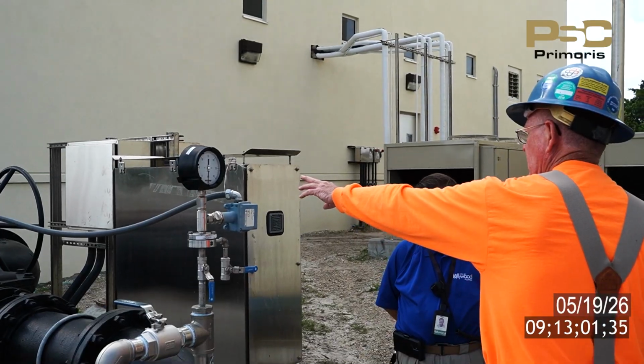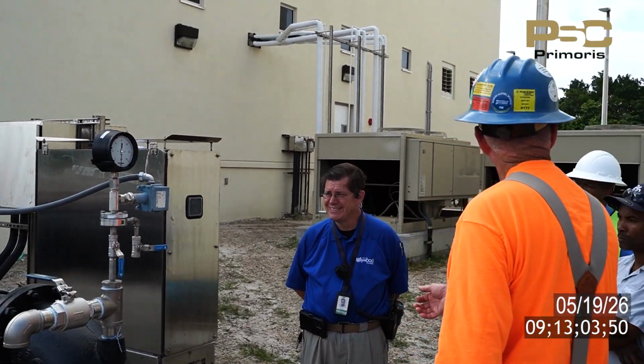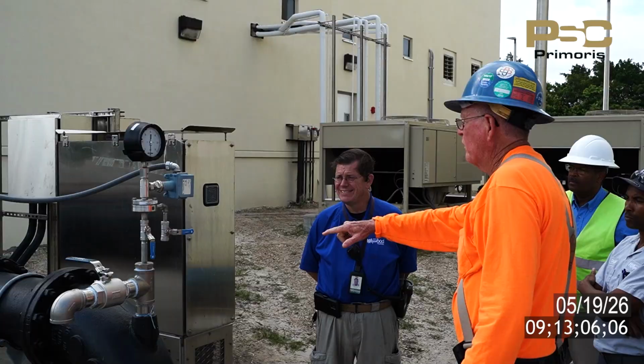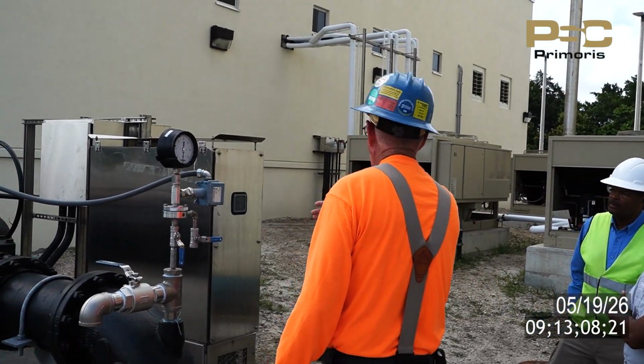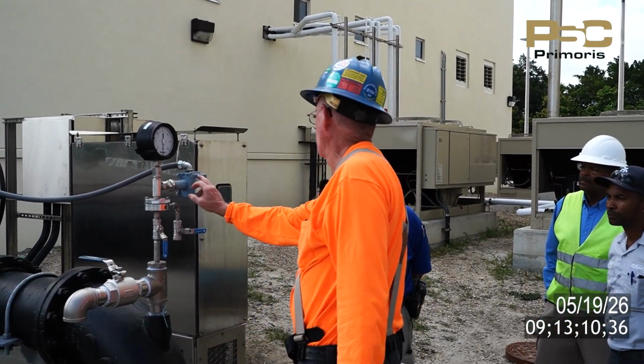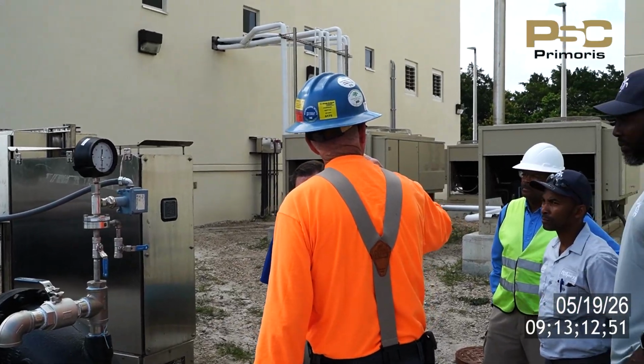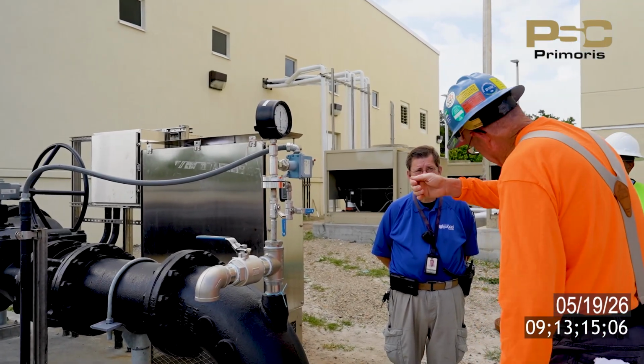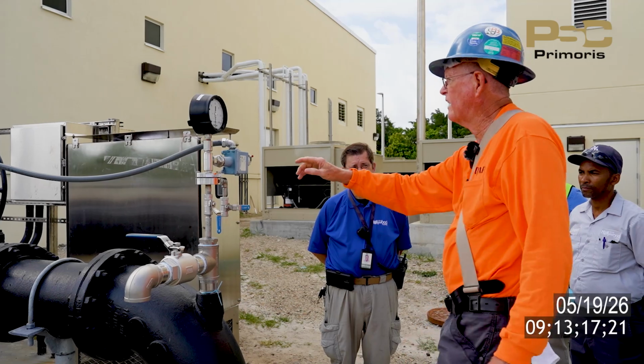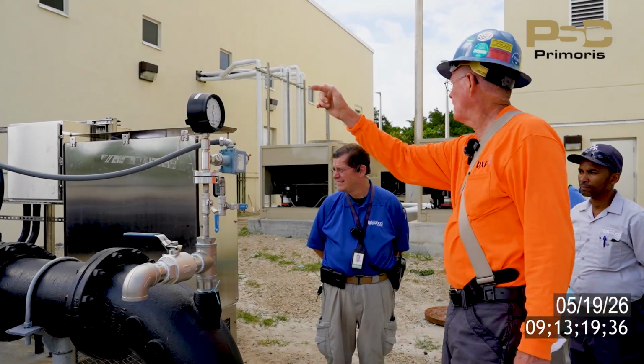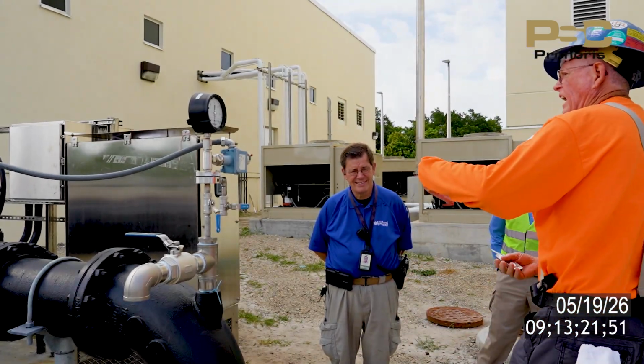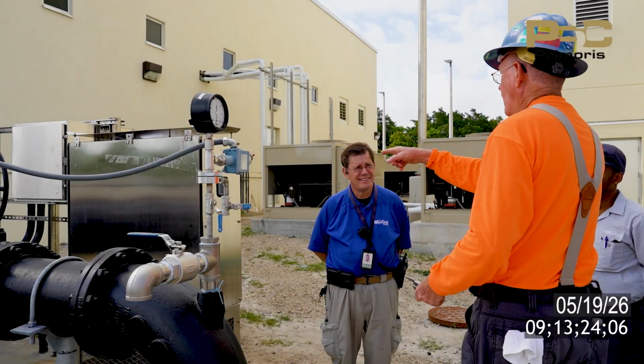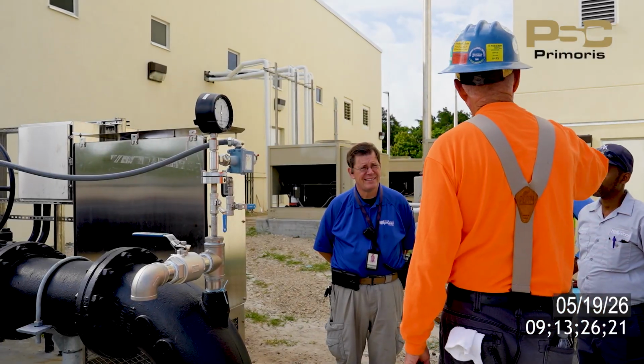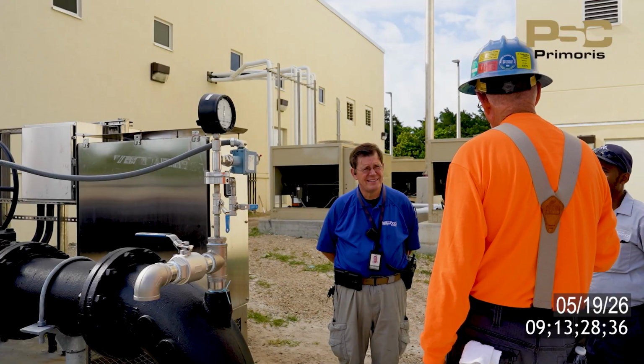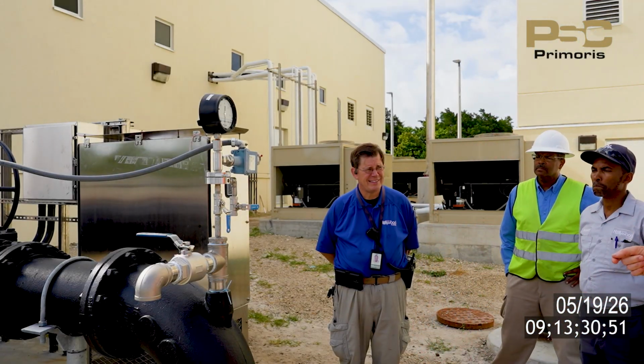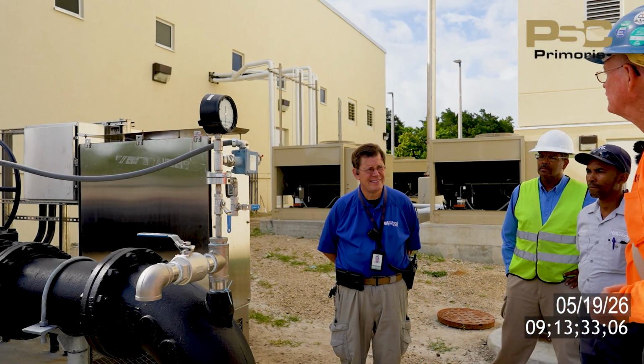So what I did was I closed the discharge valve and ran the pump. I didn't have it set right the first time, so it kept running. I had to lower the switch down a little more, try it again, kept running, turn it again. Finally got to the point where if somebody leaves the discharge valve closed, and you put the pump back online, when it hits the pressure switch it just turns off, and as soon as the pressure drops it turns right back on. It's a non-latching circuit.